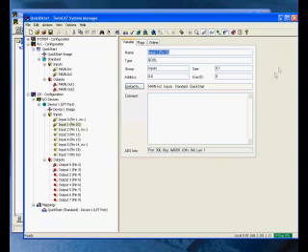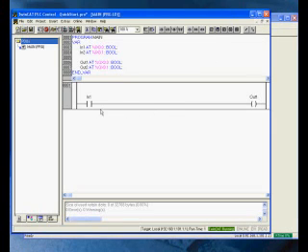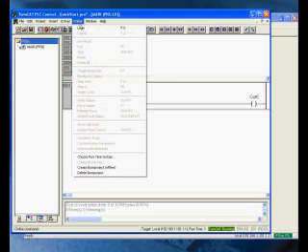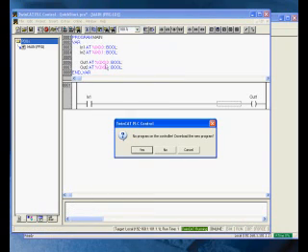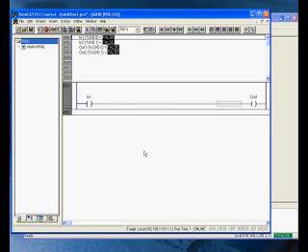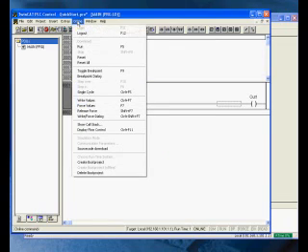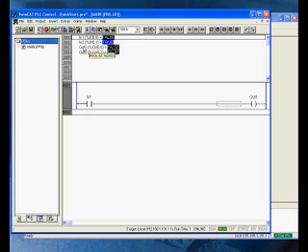So now when I restart it, you see down in the bottom it is in run mode, which is the system, not the PLC. So now I'm going to go back to PLC control, log in, and it asked me to download the program. I said yes. So now I'm going to put the PLC in run mode. Actually running. Now I'm going to double click these contacts and do an F7, which is a shortcut for force.